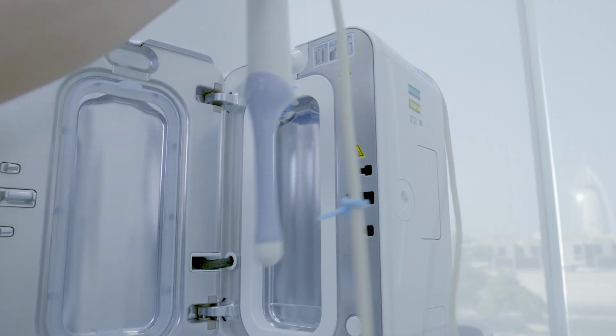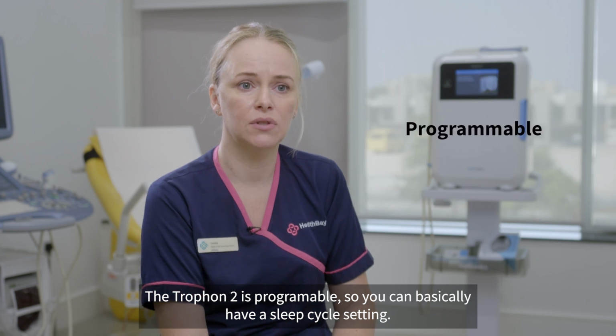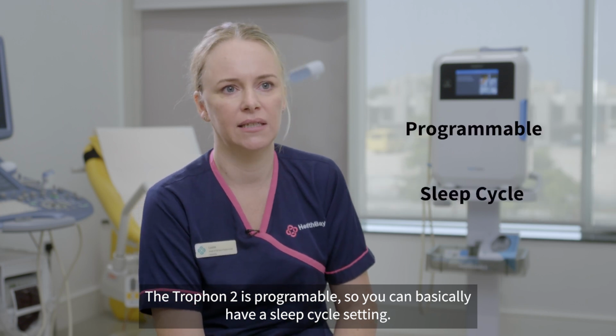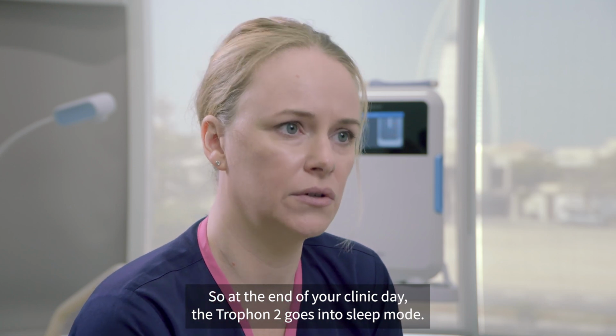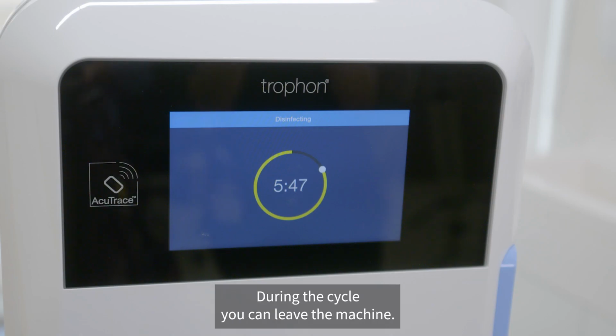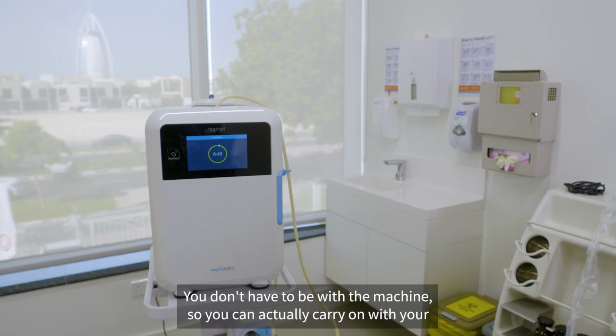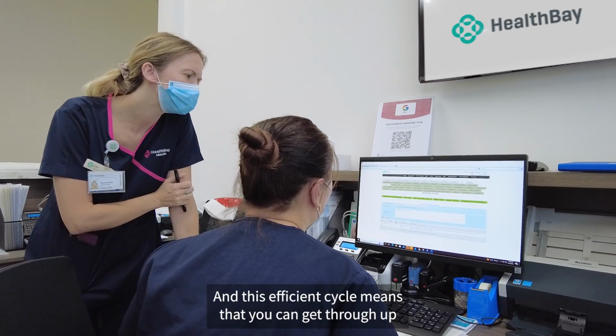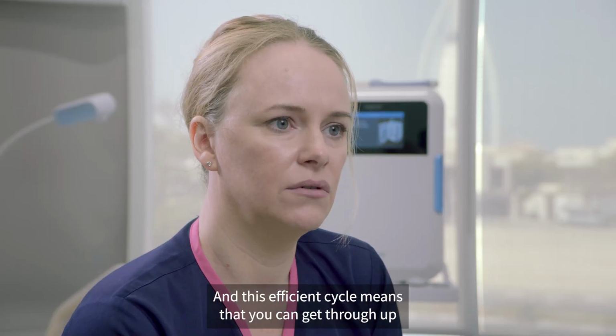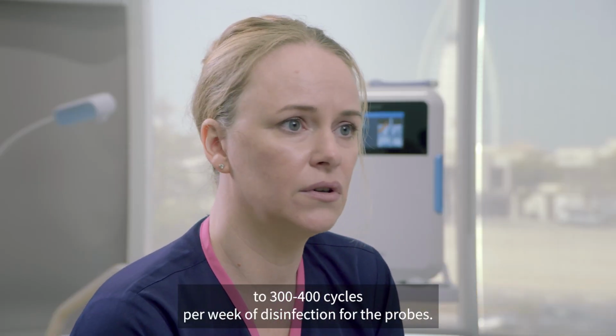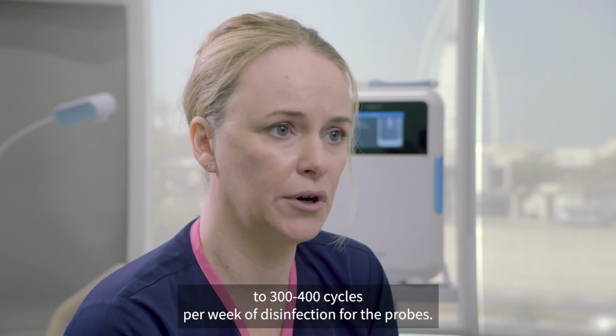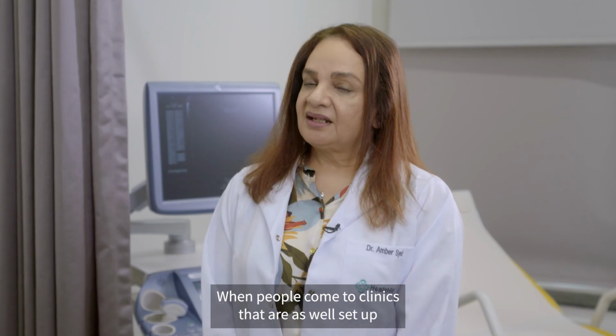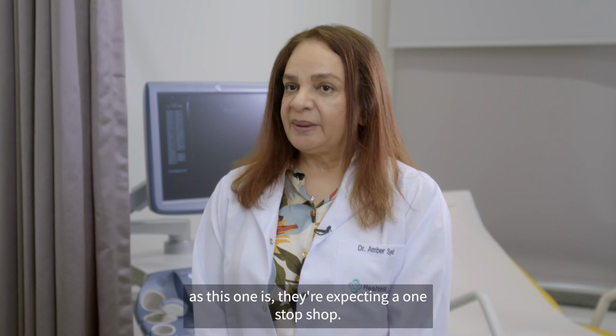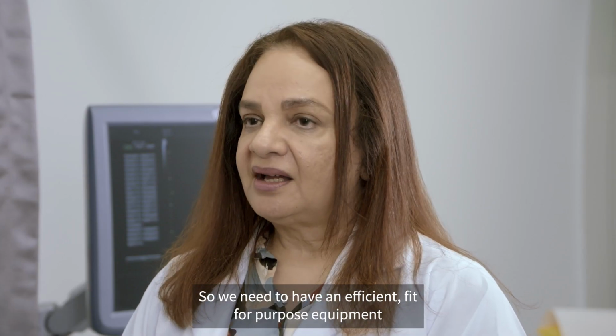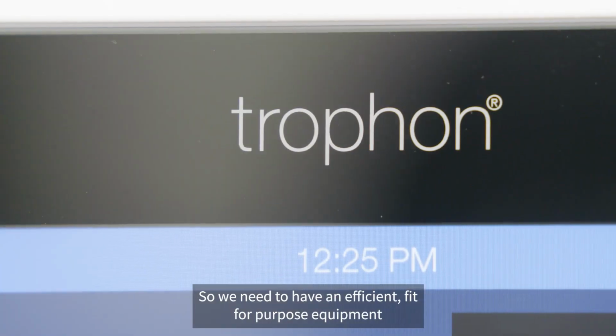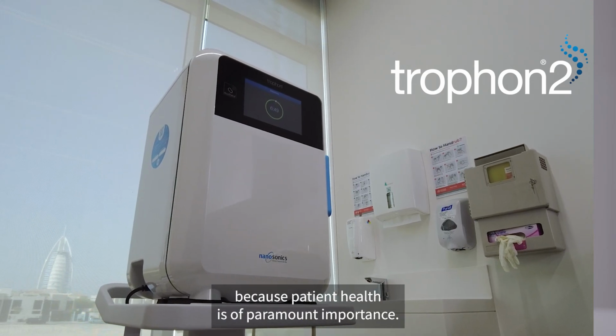The Trophon 2 is programmable, so you can basically have a sleep cycle setting. So at the end of your clinic day, the Trophon 2 goes into sleep mode. During the cycle, you can leave the machine, you don't have to be with the machine, so you can actually carry on with your day-to-day work. And this efficient cycle means that you can get through up to 300-400 cycles per week of disinfection for the probes. When people come to clinics that are as well set up as this one is, they are expecting a one-stop shop. So we need to have efficient, fit-for-purpose equipment because patient health is of paramount importance.